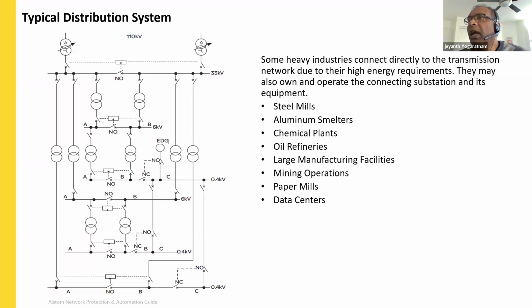When you look at this power distribution, at least a minimum of two main feeds are connected from the utility, and in some instances, this can be more than two as well. This provides reliability and helps the operation perform maintenance without causing any power outages. It is like a redundant supply, and in most cases they operate in parallel, where the tiebreaker is open. Now, if we look at this application, we get two transformers coming in that step down the 110 kV primary voltage to 33 kV. And further, two feeds come in and are interconnected with a breaker, which is always kept open, in order to reduce the short circuit fault current level.